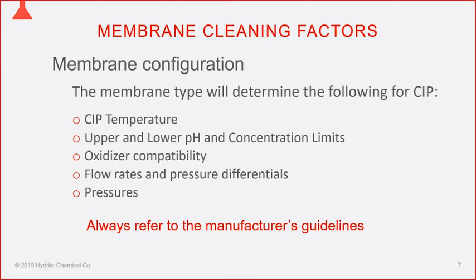A typical RO might have five membranes per vessel; a UF might have four or three. You should get a pressure differential generally around 10 to 15 psi. The greater the thickness of the flow spacers in the membrane, generally the higher that number can be. If you calculate that number for each stage and get around 10–15 psi, your hydraulics and flow are generally good. Always refer to the manufacturer's guidelines and ensure warranty compliance.